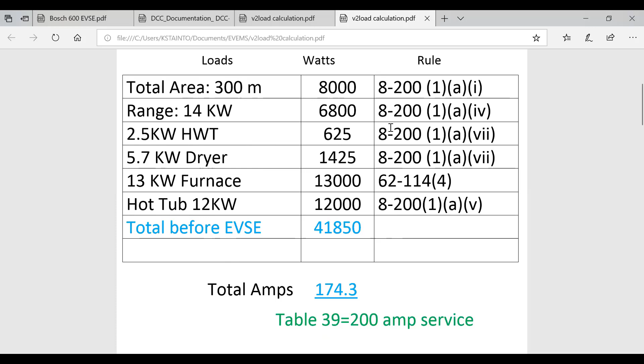As you can see, on our home prior to an EVSE being installed, we had a total wattage of 41,850 watts on a 240 system. That calculated out to 174.3 amps. If we refer to table 39 of our code book, we discovered that was a 200 amp service. So that was the service we're starting with.